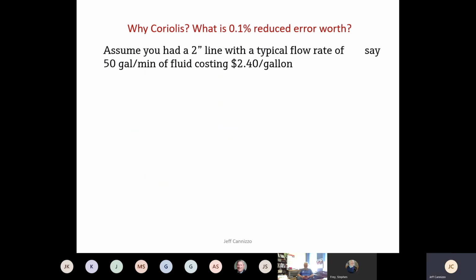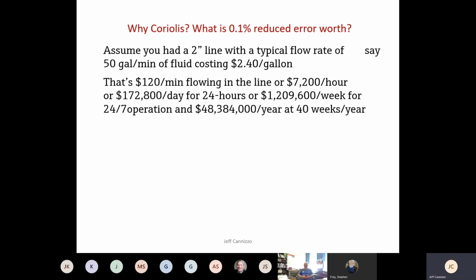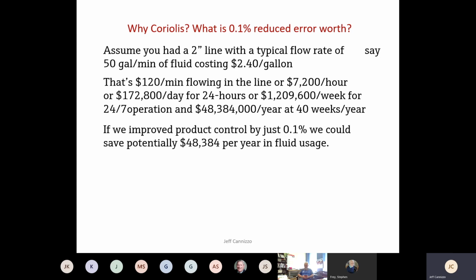So why would you even consider a Coriolis? You know that they're expensive. They are the most expensive type of meter to manufacture, and obviously cost-wise to you. But if you look at the cost of your product, a 2-inch line with a typical flow rate of 50 gallons a minute, and that fluid costs $2.40 a gallon, that ends up being about $48 million worth of product at the end of a 40-week year, 40 weeks of running on a 24/7 type operation, $48 million. So if you improve that product control by just 0.1%, that's $48,000 a year of potential savings.